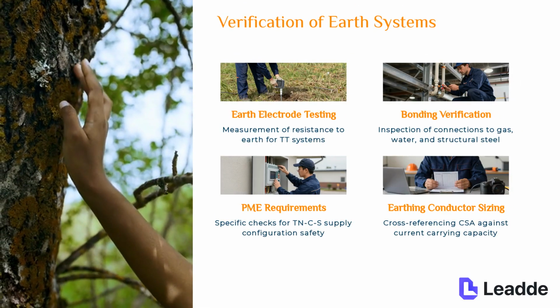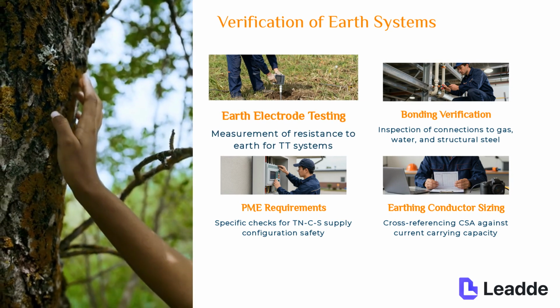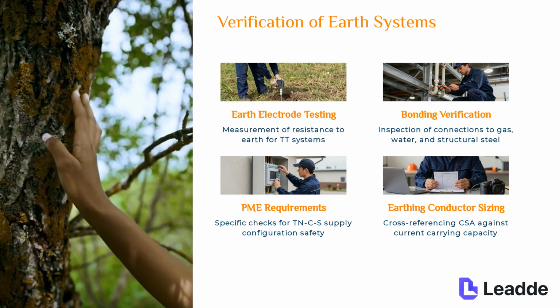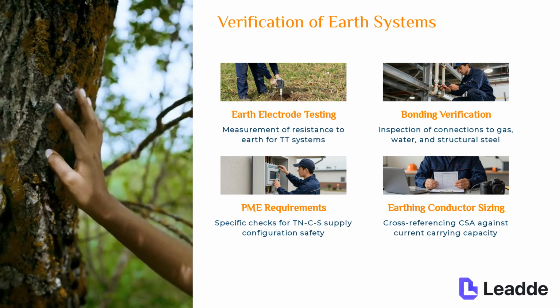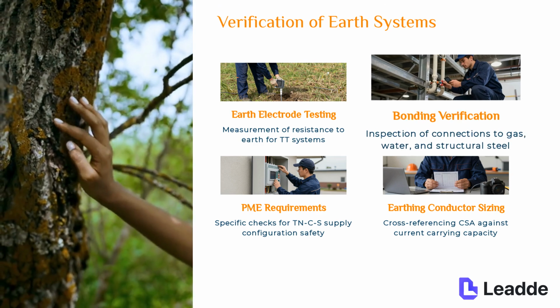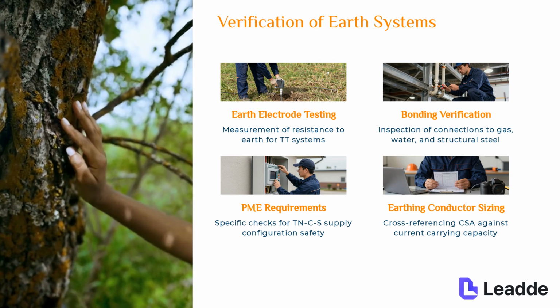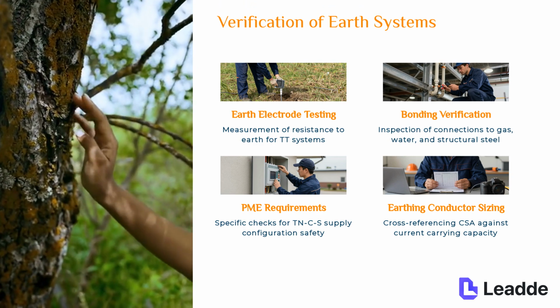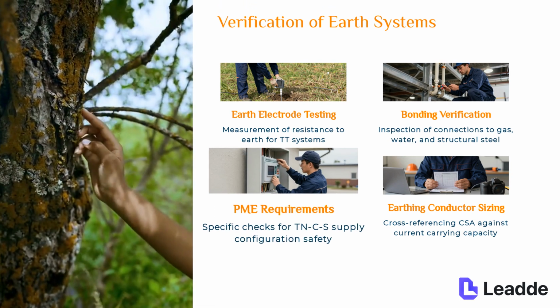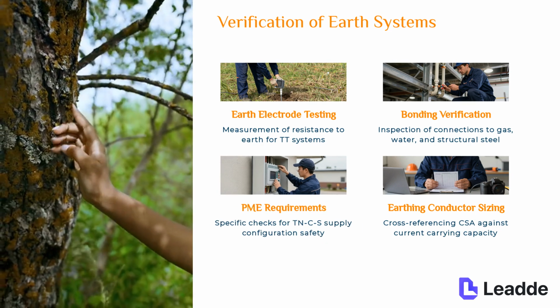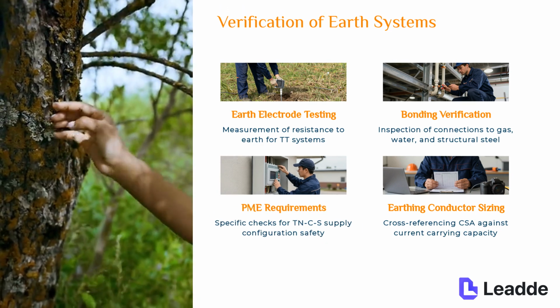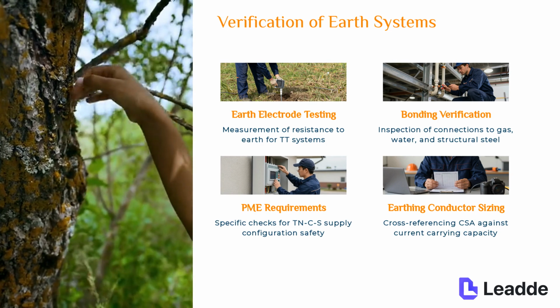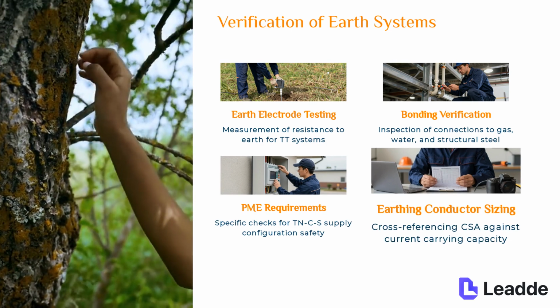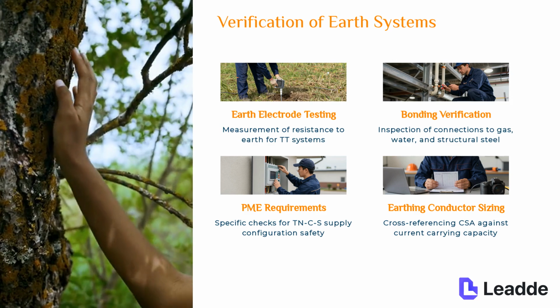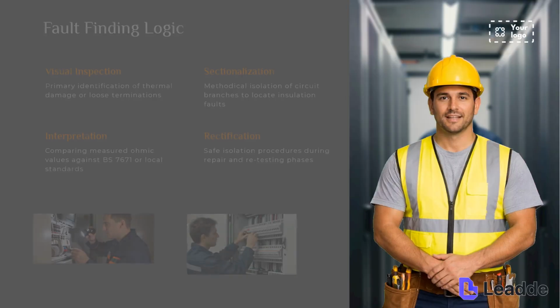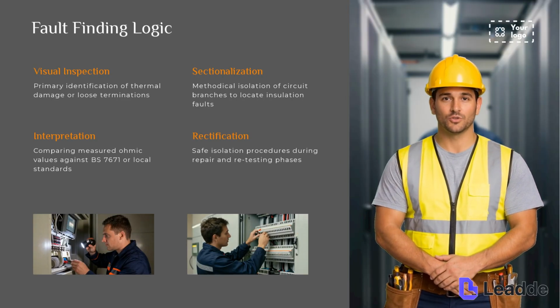This involves the measurement of resistance to earth for TT systems through earth electrode testing. It also includes the inspection of bonding connections to gas, water, and structural steel. For TNCS supply configurations, there are specific checks required to ensure PME safety. Finally, we must cross-reference the cross-sectional area, or CSA, of earthing conductors against their current carrying capacity to verify correct sizing. A logical approach to fault finding is crucial.